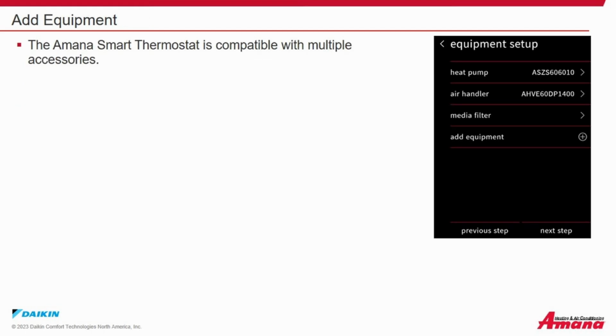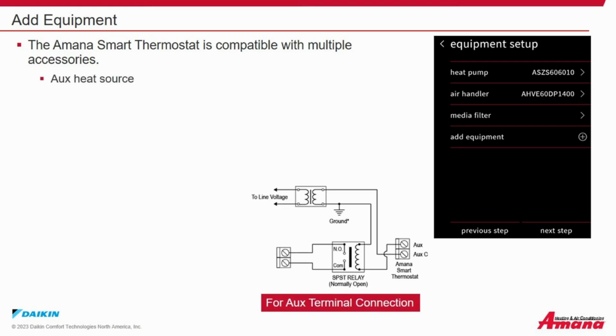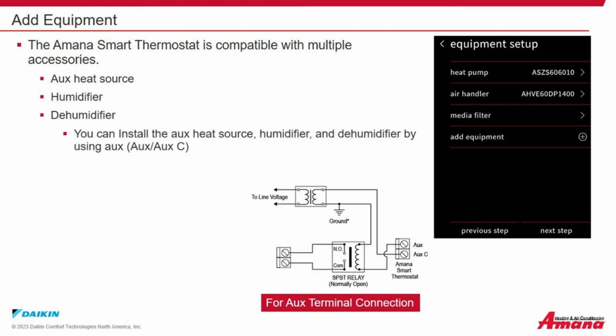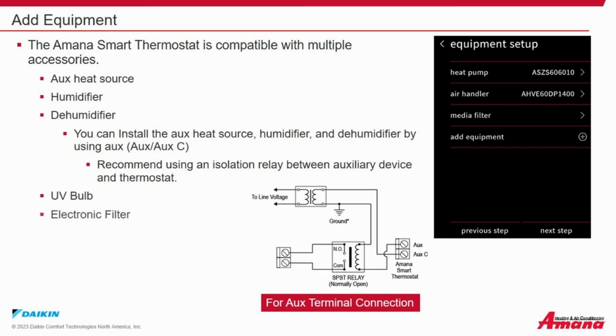Add equipment. The Amana Smart Thermostat is compatible with multiple accessories, such as auxiliary heat source, humidifier, dehumidifier. You can install auxiliary heat source, humidifier, and dehumidifier by using auxiliary and auxiliary C terminals. Recommended using an isolation relay between auxiliary device and the thermostat. UV bulb, electronic air filter, HEPA filter, EWC zone board, and a 24-volt gateway.